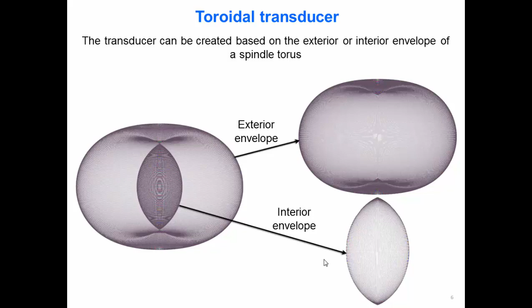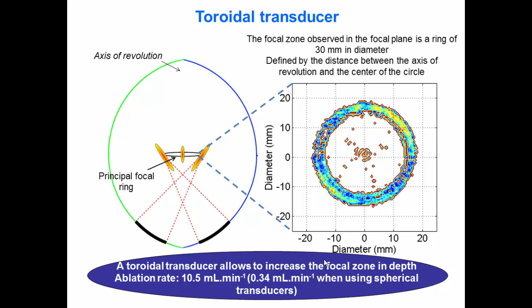And the difference of the focusing regarding a spherical transducer is that the focus is not an ellipsoid, but is a circle. And the radius of this circle is defined by the distance between the axis of revolution and the center of the circle. Most importantly, the ultrasound beam intersects between this principal focus and the transducer and forms a secondary focal zone, which contributes to increase and reinforce the ablation volume.